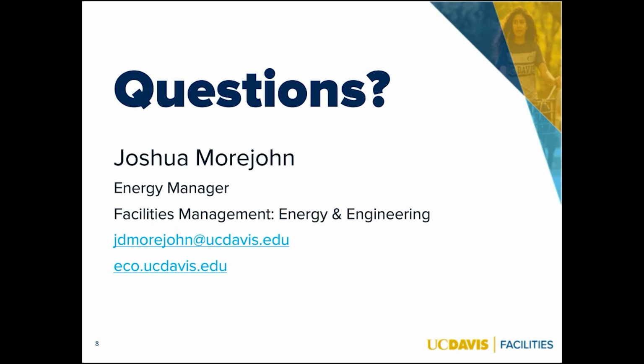Steve, do you want to address that? Yeah, it really depends a lot on the relative price of gas and electricity. It tends to be better for buildings heated with propane than natural gas, and depends on the local price of electricity. There are quite a few buildings in our sample in cold climates with reasonable paybacks, but the better paybacks are much more so in the south. There are some examples where it pays back in the north, but it very much depends on local prices. I'd also note, in response to some questions, that in the north we generally assumed use of some of the best cold climate heat pumps currently available—not the same heat pump everywhere, but units with good cold climate performance.